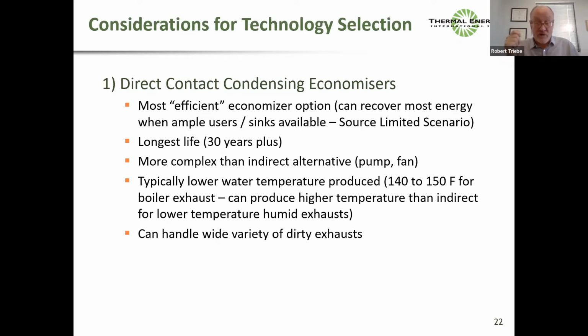So we call that a source and sink limited situation. When you have more user than source, then this is the best technology because it can squeeze the most heat out of the source. It's also got the longest life. That's because the acid drops that develop when you're condensing, the small acid drop is immediately neutralized in a huge shower of water. So you don't get spot corrosion, spot condensation. However, with this type of system, you typically need a fan and a pump, whereas sometimes indirect contact systems can go in without a fan and a pump.